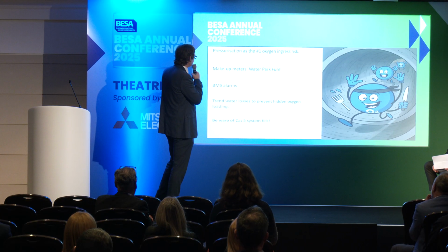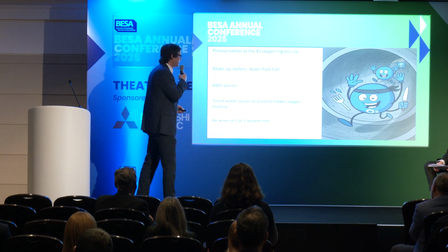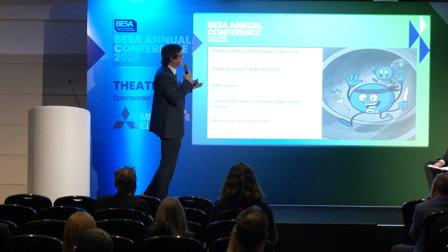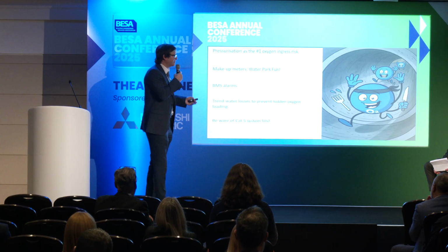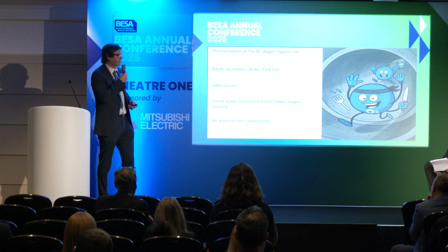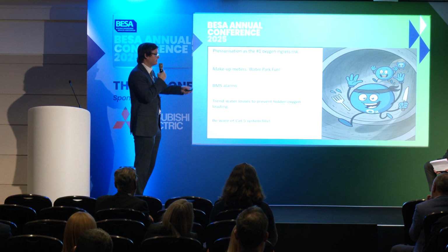You've got things like your BMS alarms, trending water loss to prevent or catch hidden oxygen loading, and that's the biggest one. You can have situations where certain pieces of equipment are letting water by and you're filling it up, and if you don't monitor it, that's what's happening, isn't it, David?